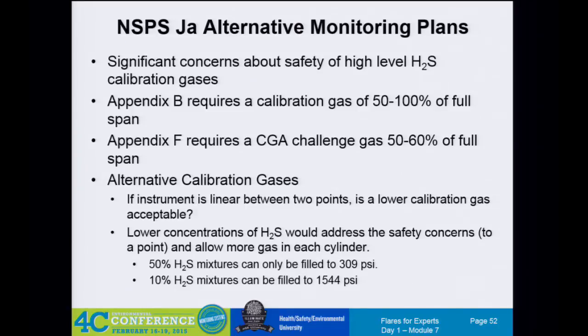And we have heard that a couple of the instrument manufacturers have done the testing to show that their instruments are linear over the entire range. So can you take that information and request an AMP and say, they've shown that they're linear, why can't I use 2 points with much lower concentration gas and use that for my daily cals? Again, it's a great idea. It requires an AMP. We found out that one refinery has requested this AMP, but they have not heard back yet on that AMP. So we think it's a great idea. We think all of you should do it.